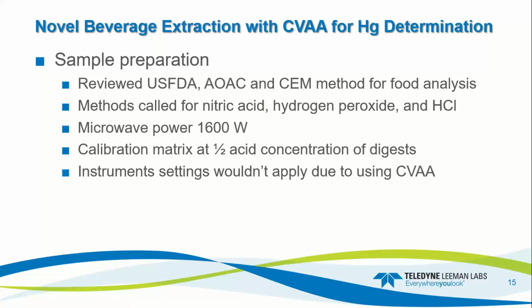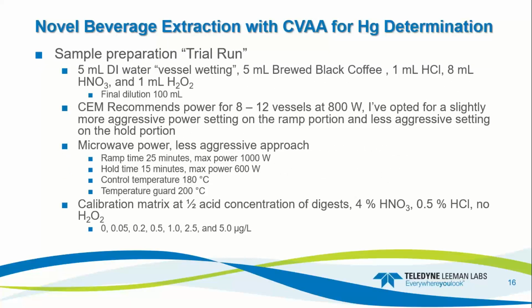Sample preparation. I reviewed US FDA, AOAC, and CEM methods for food analysis. These methods called for nitric acid, hydrogen peroxide, and hydrochloric acid, microwave power at 1600 watts, and a calibration matrix at 1/2 the acid concentration of the digest. The thought process here is that some of the acid is going to be consumed during the digest. So in order to matrix match, they opted for cutting the acid concentration in half, assuming that would be approximately equal to the percent acid within the final diluted volumes of sample. And within these methods, the instrument settings wouldn't apply because we're opting for the cold vapor atomic absorption technique for the determination of mercury.